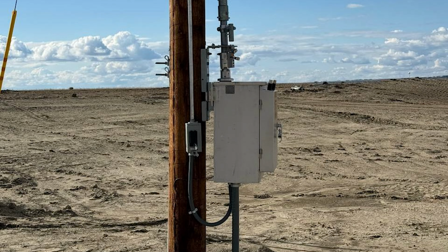So what we ended up doing was putting up a pole and putting a disconnect on that pole, and then running it down. Rather than going from the primary directly to the transformers, we had to go from the primary meter up to a pole with a disconnect, and then from that pole and disconnect down to the transformer. So that's what they ended up doing over there.